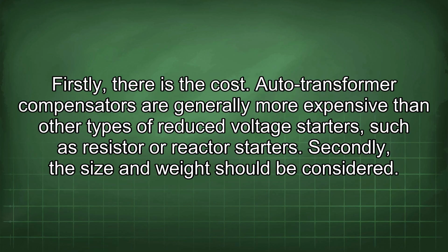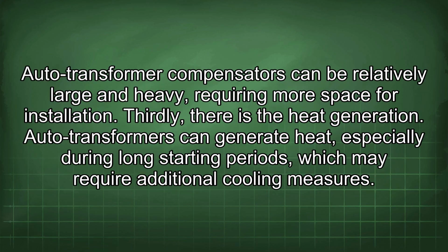Secondly, the size and weight should be considered. Auto transformer compensators can be relatively large and heavy, requiring more space for installation. Thirdly, there is the heat generation. Auto transformers can generate heat, especially during long starting periods, which may require additional cooling measures.